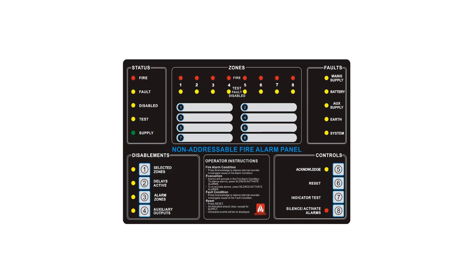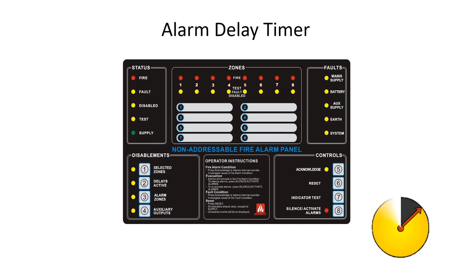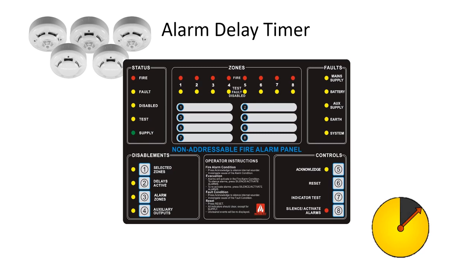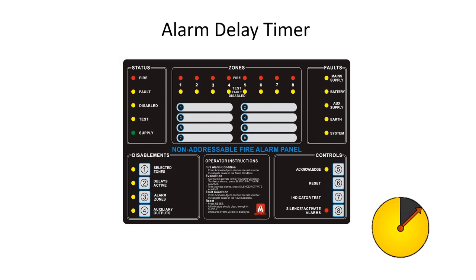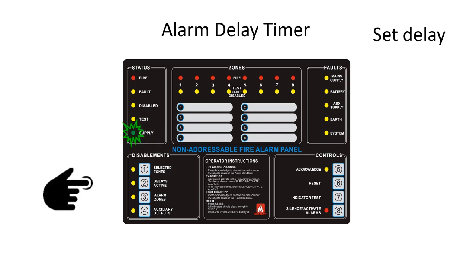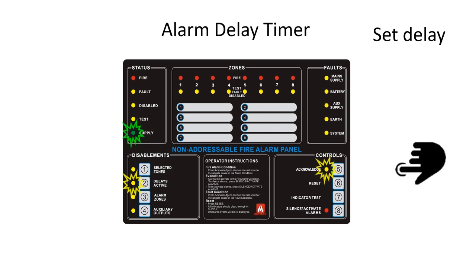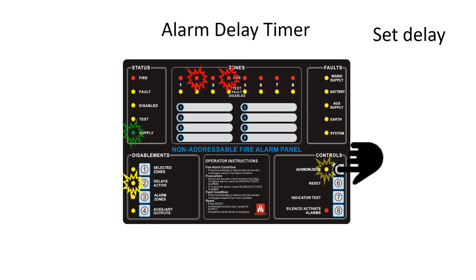If the system design requires a delay before alarm devices are activated, there is a 2-step process to configure the delay. The first step is to set the delay time, and then assign the delay timer to one or more detection zones. To configure an alarm zone delay, enter access level 3 and press the Delays Active button. The Delays Active LED and the Acknowledge LED will both flash. Press the Acknowledge button to confirm.